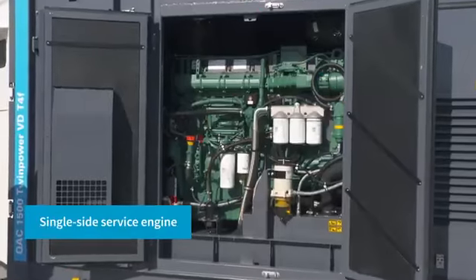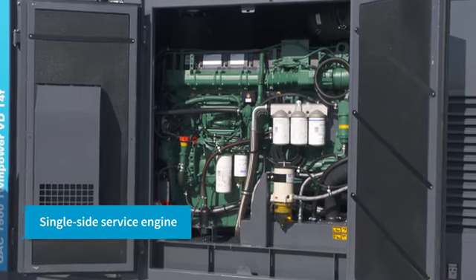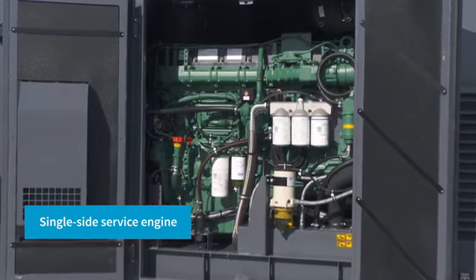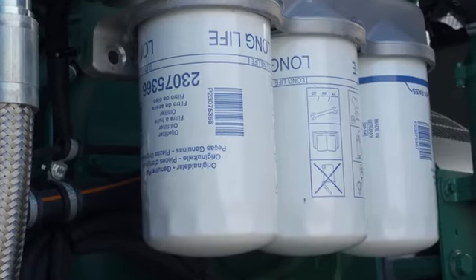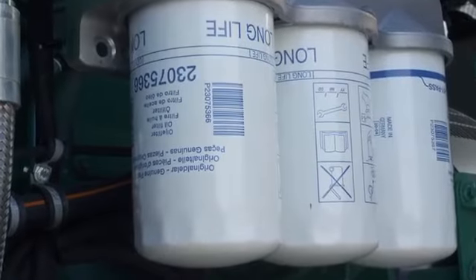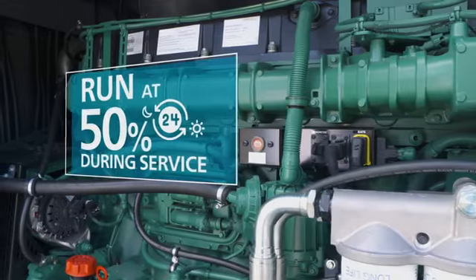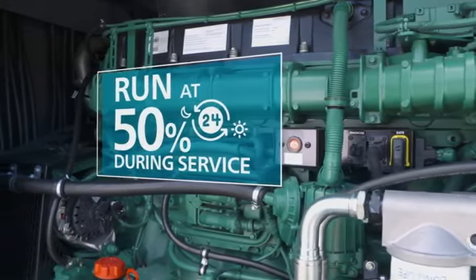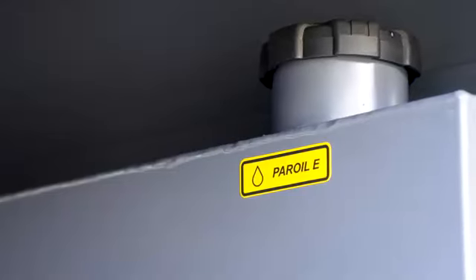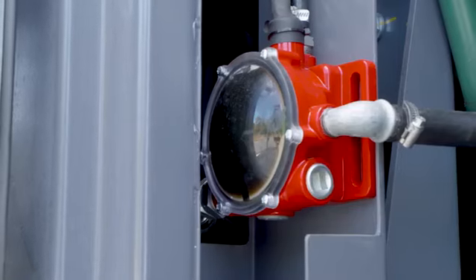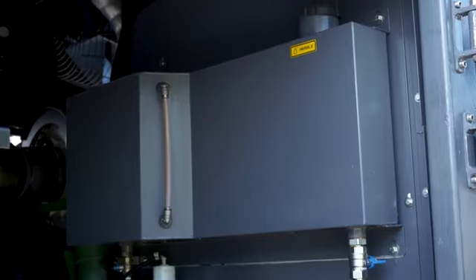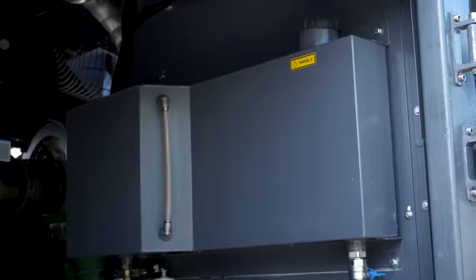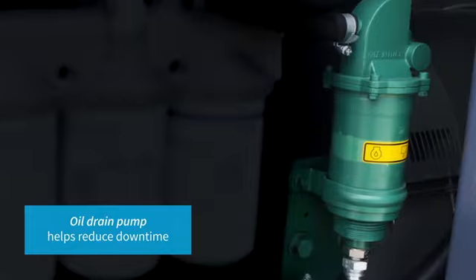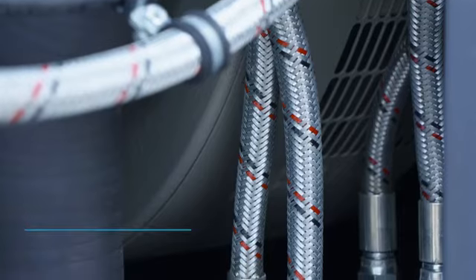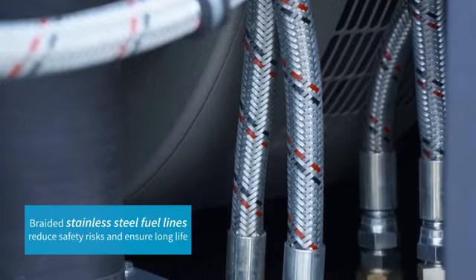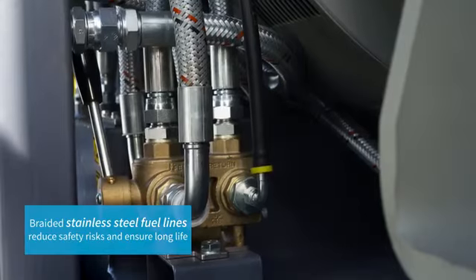Serviceability. It has a true single-side service engine. Oil and fuel filters have been moved to one side to ensure service work can be executed quickly and efficiently, reducing cost and downtime. Either engine can be serviced while the other engine remains running, ensuring no blackouts anytime. Internal oil tanks, coupled with the Murphy Oil Level Maintainer, ensure that oil refill will not be necessary between service intervals. Plus, the oil drain pump will help reduce the downtime during service, and the braided stainless steel fuel lines reduce safety risks and ensure a longer life.